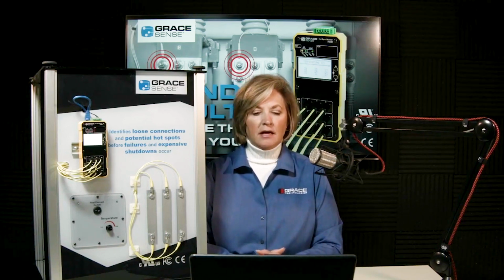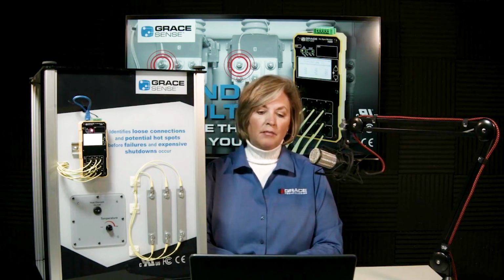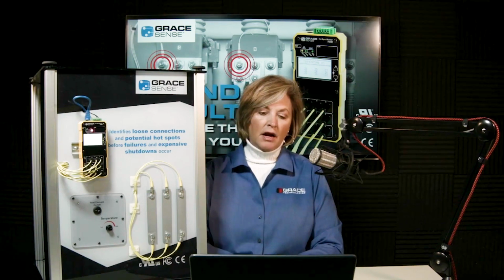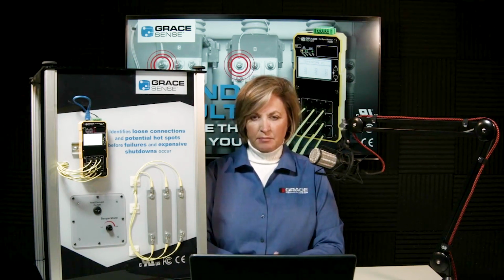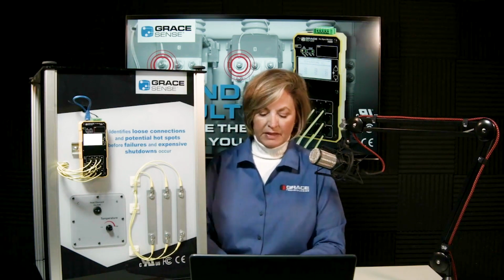In recent years, I've been asked questions like, where do I install them? Do I install them on all bolted connections? And in this day and age, really, it's anywhere that has human interaction, human contact, or is inaccessible, or locations that are kind of hidden, either from real estate constraints where your equipment is up against a wall, or in situations where that human contact is going to be there. We want to really take those points that might have some extra vibration issues, some points that, again, are covered with barriers or have cable terminations in locations like this.